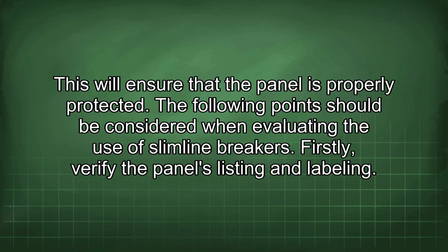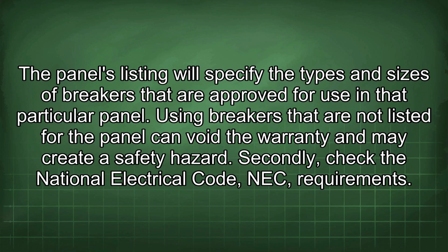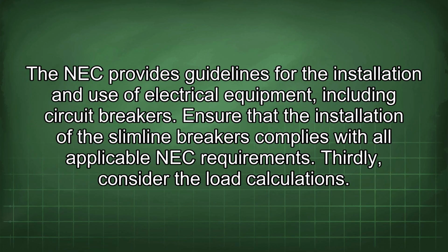The following points should be considered when evaluating the use of slimline breakers. Firstly, verify the panel's listing and labeling. The panel's listing will specify the types and sizes of breakers that are approved for use in that particular panel. Using breakers that are not listed for the panel can void the warranty and may create a safety hazard. Secondly, check the National Electrical Code (NEC) requirements. The NEC provides guidelines for the installation and use of electrical equipment, including circuit breakers. Ensure that the installation of the slimline breakers complies with all applicable NEC requirements.